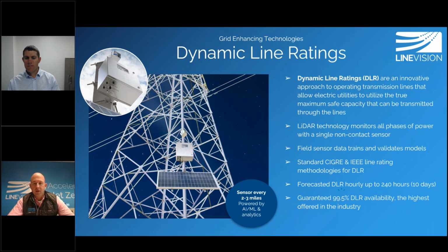This is consistent with how everybody around the world is rating their lines today. We're using standard CIGRE and IEEE rating methodologies, but instead of using those assumed variables for outside conditions like air temperature or wind speed, we're actually using this data to inform exactly what those values are. And so with that, you have an accurate understanding of what you can do with your grid. And it's very consistent with everything that's happening in the industry already.